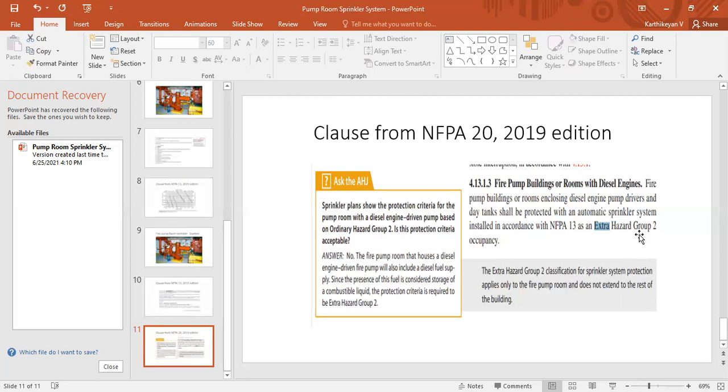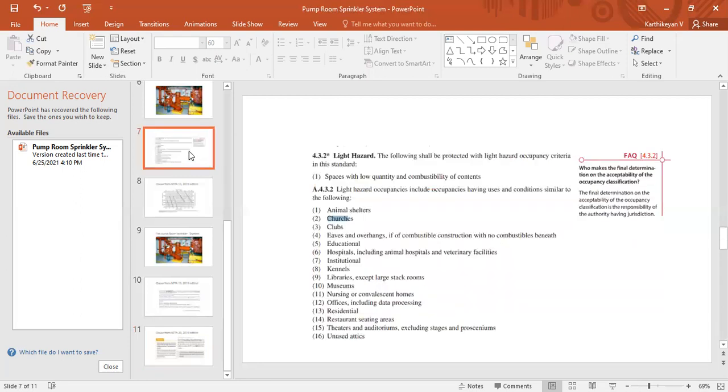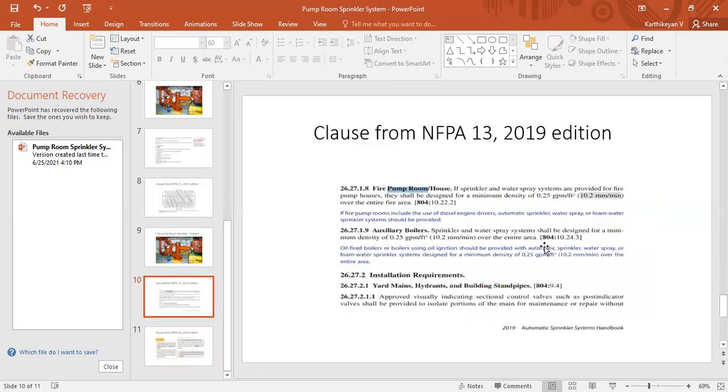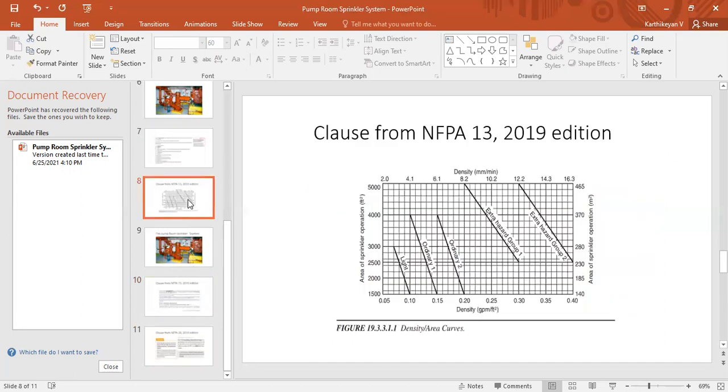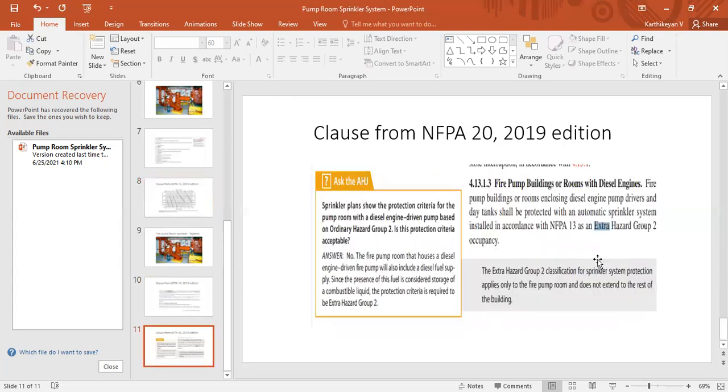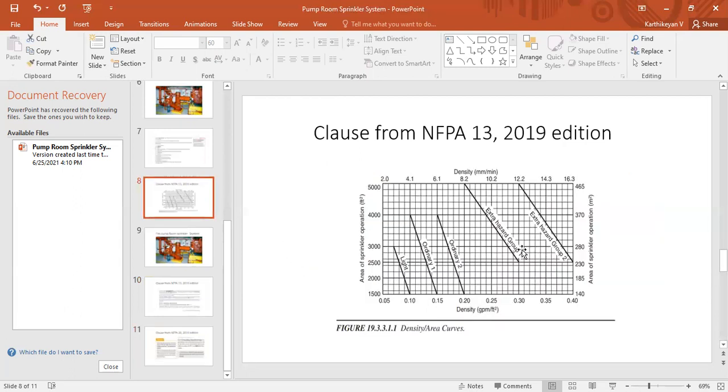So I'm clearly stating here, NFPA 20 says fire pump room should be extra hazard group two. Here the question will arise: NFPA 13 says it is 10.2. If you are checking with this curve, it clearly says extra hazard group one. So it is a contradiction because here it says group two, here it says group one. So which one is correct?